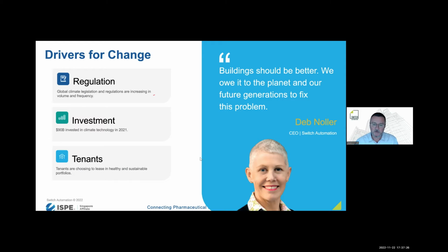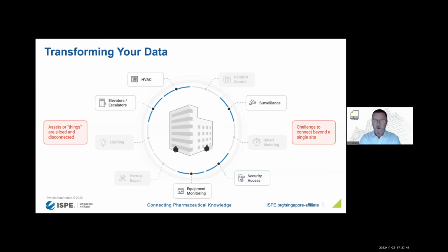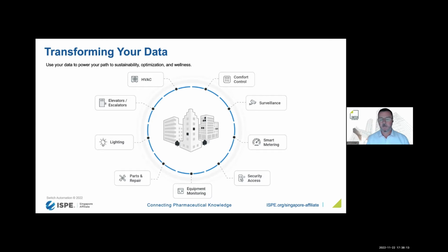What we aim to do with a digitalization program is put the data back in the hands of not just the owners and operators of the building, but also the people that live, work, and operate in the building. We do that by breaking down silos. Those of you who work in and around building operations will know we have lots of systems, particularly in the pharma industry, and all of those systems are disconnected. The BMS system doesn't talk to the access control system, it doesn't talk to the elevators or vertical transport, and it doesn't talk to the fire alarm system or the lighting systems. As a result, you don't get the opportunity to bring the data into a single place and optimize the building based on many metrics instead of just one.